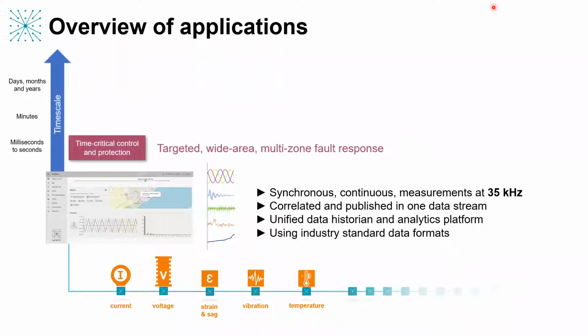There's a number of different things we can do with that, and we tend to think of them as broken into different timescales of use. The fastest use of that data would be for immediate time-critical protection and control functions. For example, replacing what a relay would traditionally do, calculating fault location, delivering effectively multi-zone fault response over wide areas. And we've got systems out there that are doing this today.